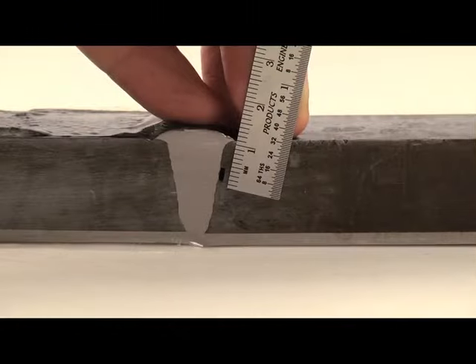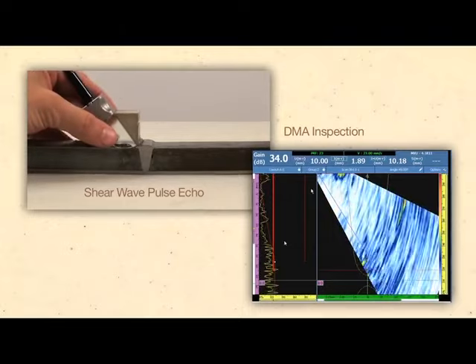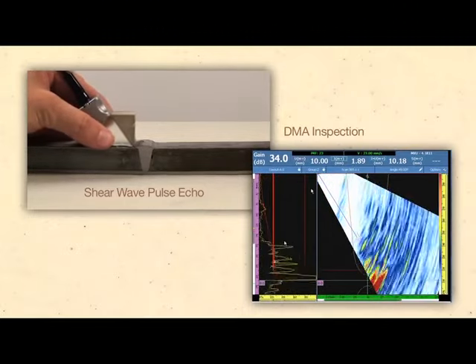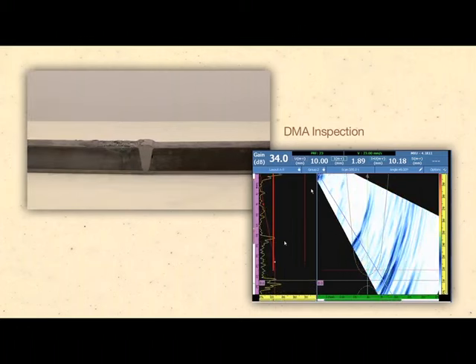Detection and sizing accuracy limits for any material or weld bevel is dependent on many factors including the probe frequency capable of detection and can only be determined through trial and error on weld samples or reference blocks of the same material.